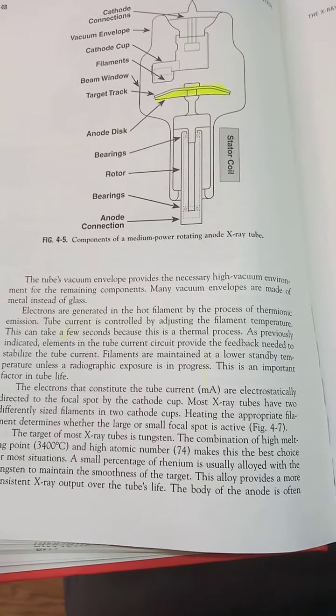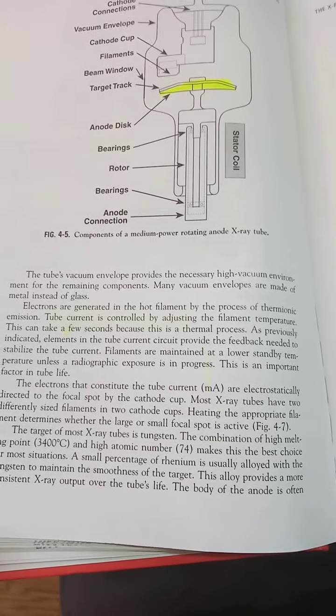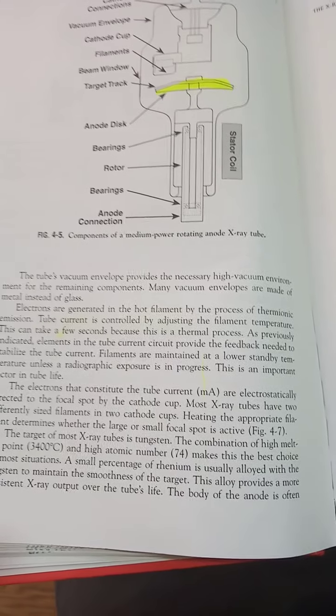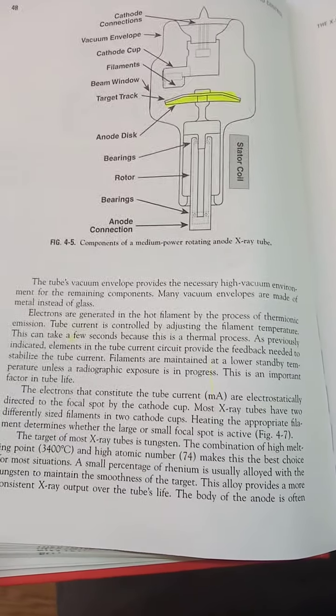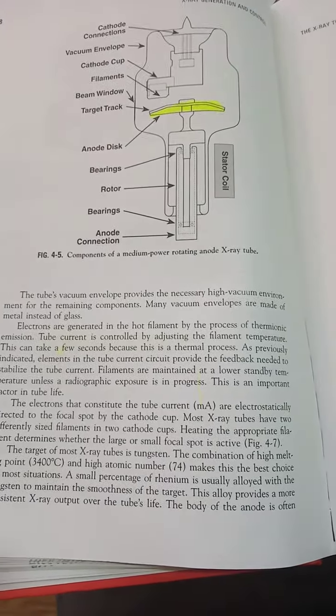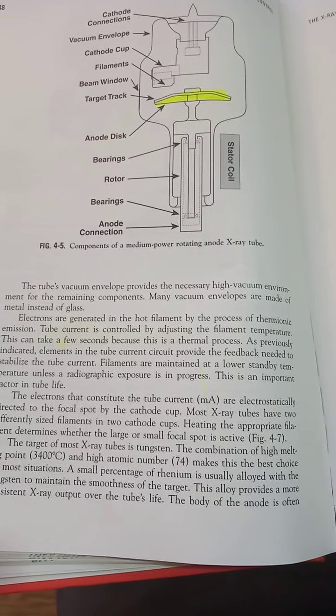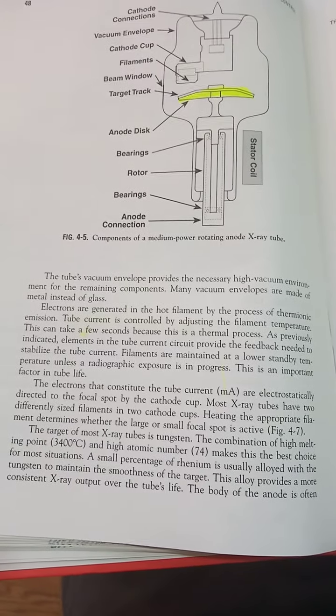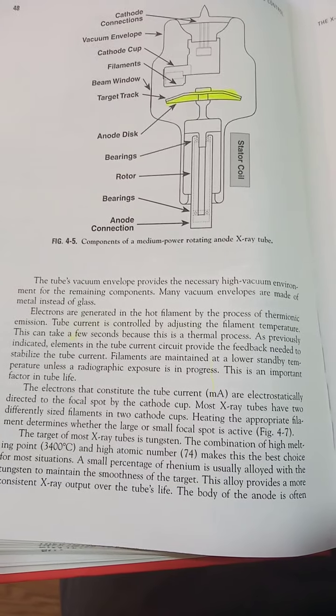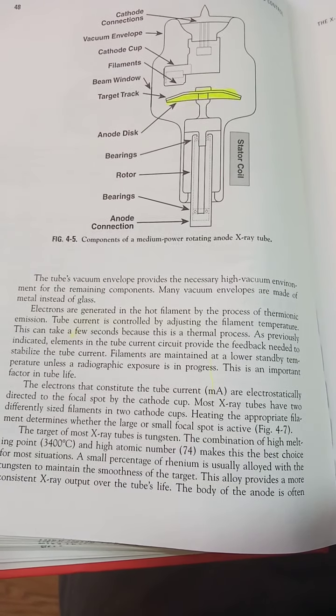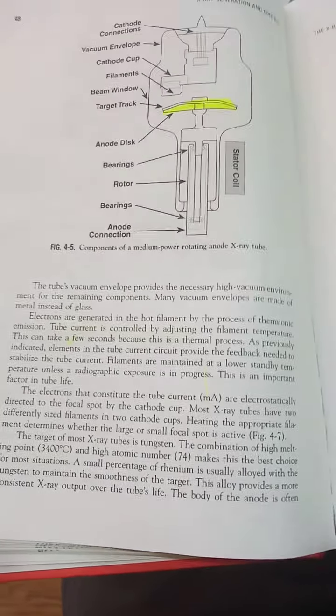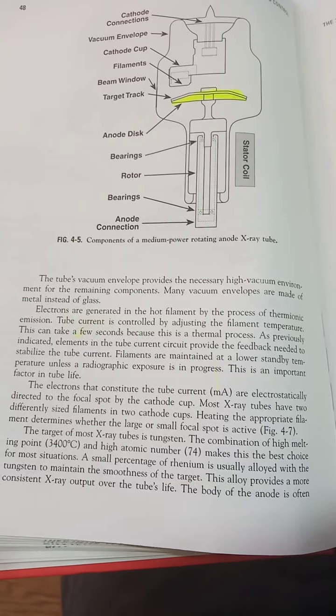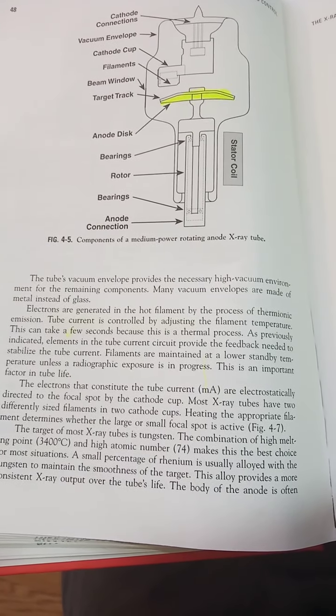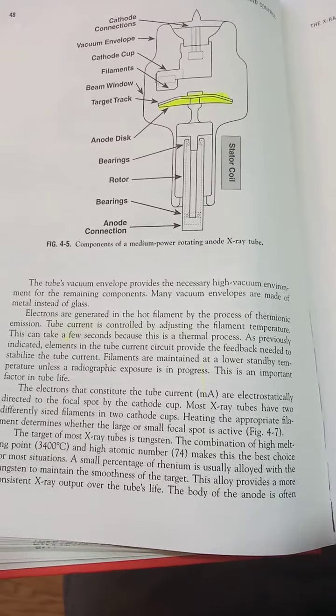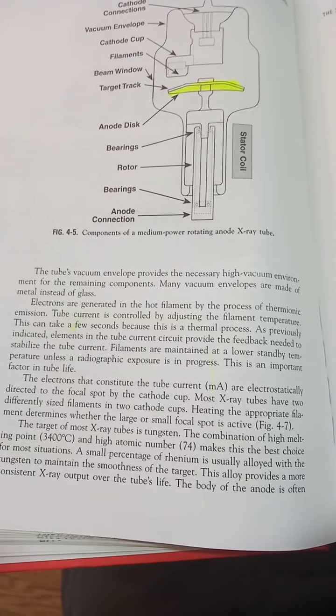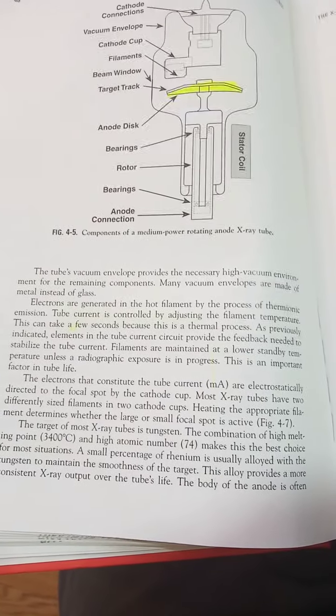Electrons are generated in the hot filament by the process of thermionic emission. Tube current is controlled by adjusting the filament temperature. This can take a few seconds because this is a thermal process. As previously indicated, elements in a tube current circuit provide the feedback needed to stabilize the tube current. The filament is maintained at a lower standby temperature, and this is an important factor in tube life.